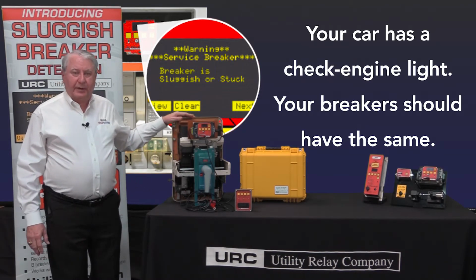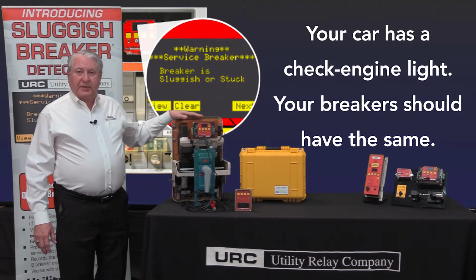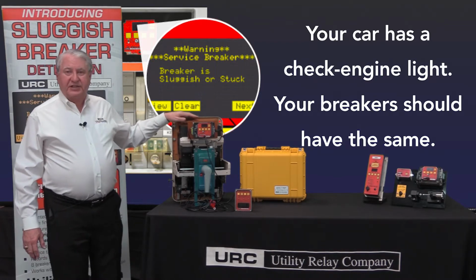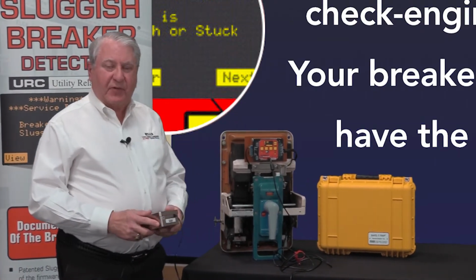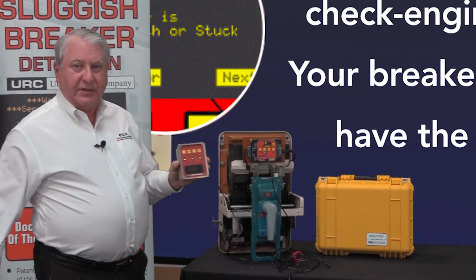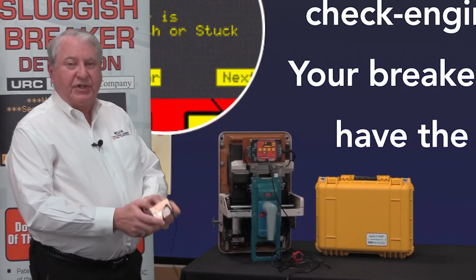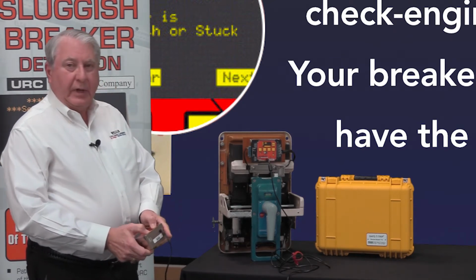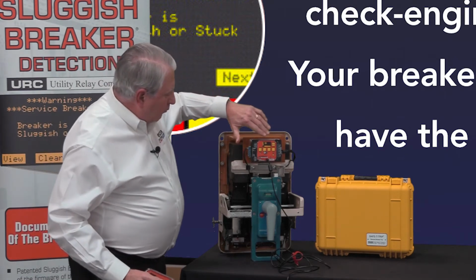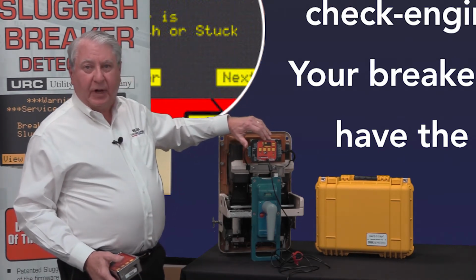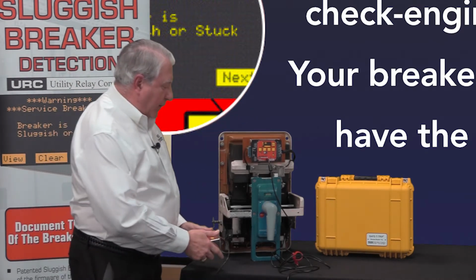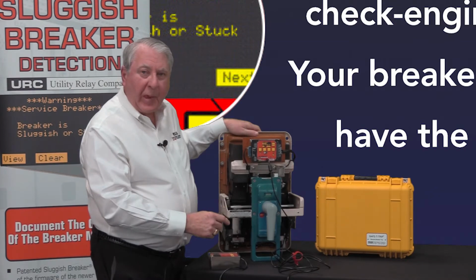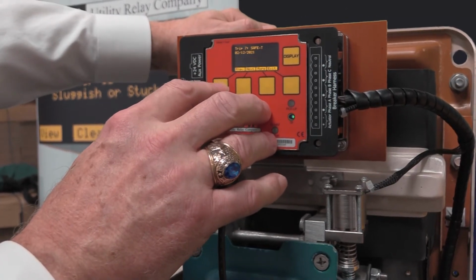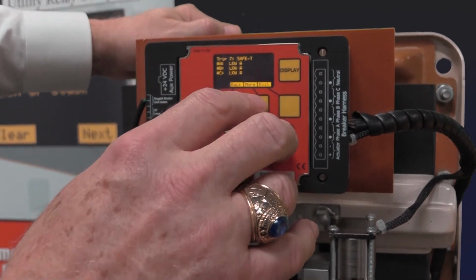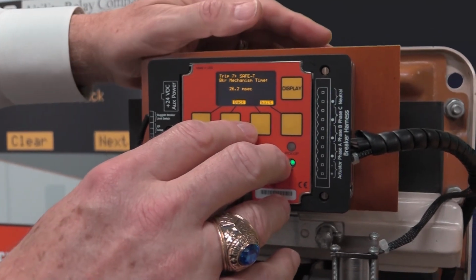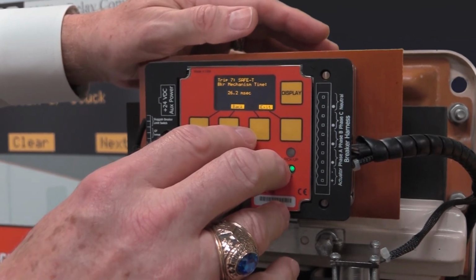We've got an AK breaker here that's retrofitted and equipped to show both sluggish and non-sluggish operation. So right now I've got it set up for non-sluggish. And I've got the SAFE-T trip activated. I'm going to push the two buttons to trip the breaker. And the breaker's tripped. And you've got no message showing on the display. In fact, you can go to the display and look at the timing of that particular opening. And as you can see, it is less than the threshold that's programmed into this, which is 27 milliseconds.